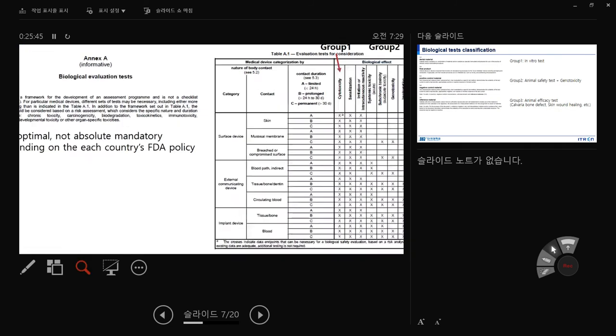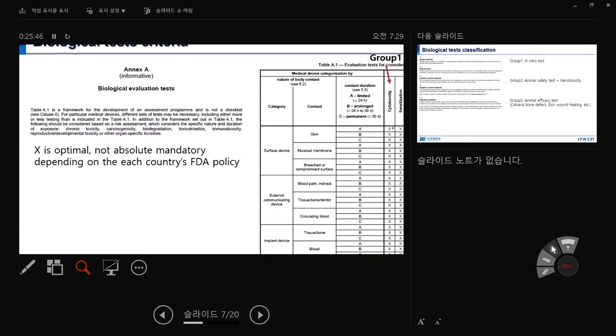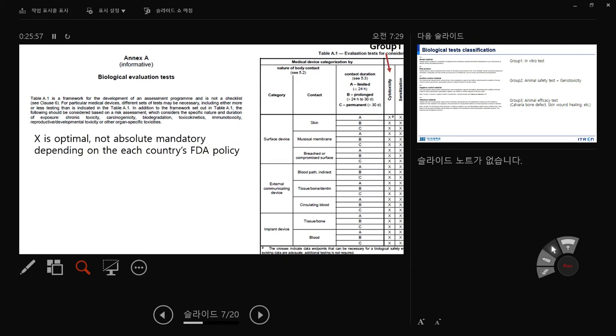Annex A is a framework for development of an evaluation program. It's not a checklist — the 'X' markings you'll see are optional, not absolutely mandatory, depending on each country's FDA policy. You need to understand this table deeply. The contact time points are: A = less than 24 hours, B = up to one month, C = over one month or permanent.